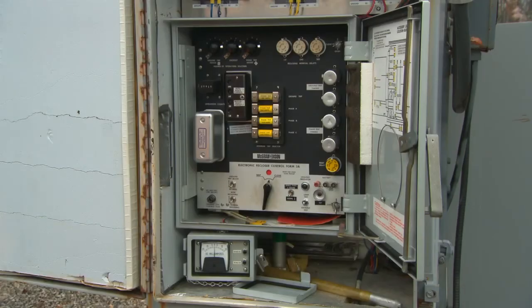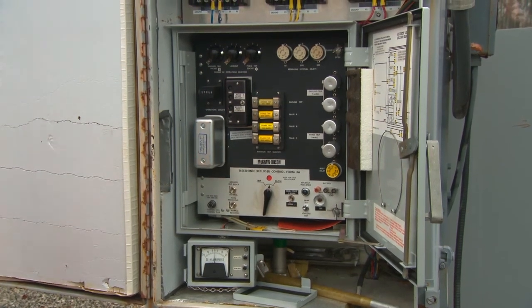This will be a basic overview of one of the first types of electronic controllers. This is an electronic McGraw-Edison Form 3A control, used in conjunction with a Cooper WVE38 recloser. The unit has separate trip coils. It also has separate ground and phase resistors, which are used on this unit to provide the trip amperages. These were the very first type of electronic controls.